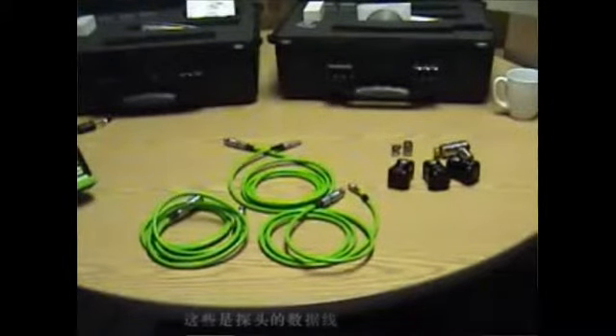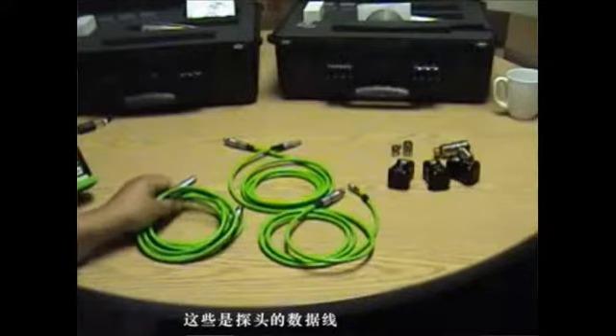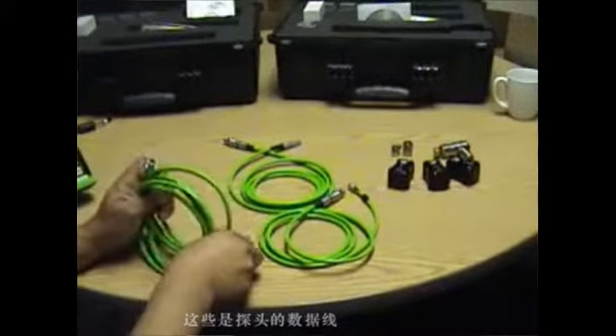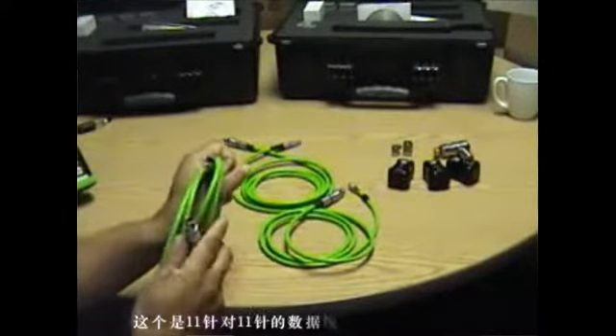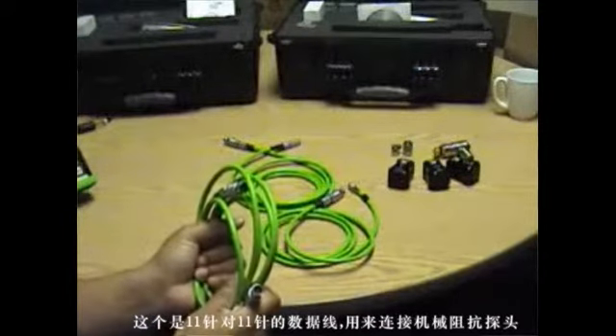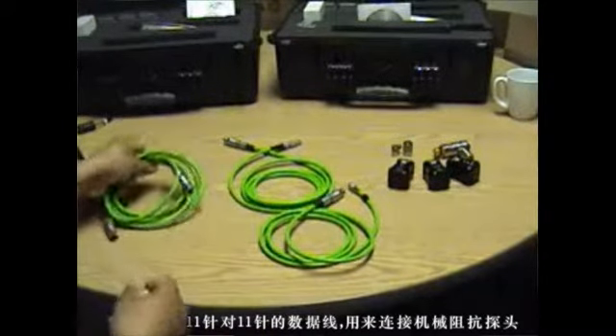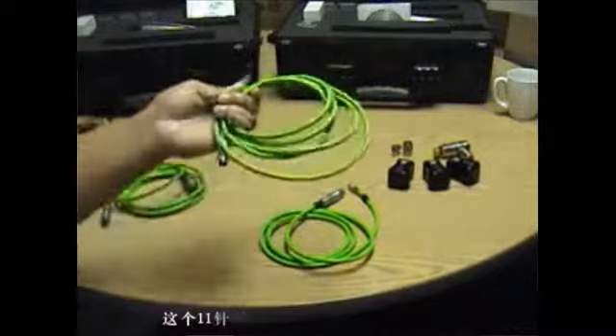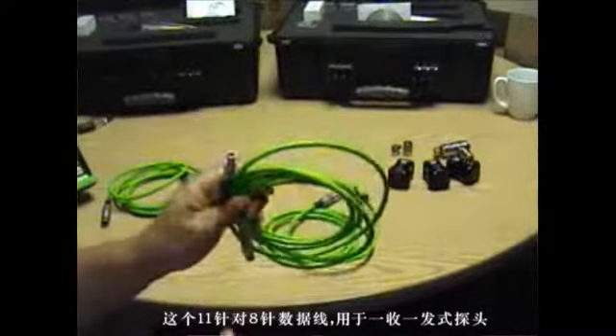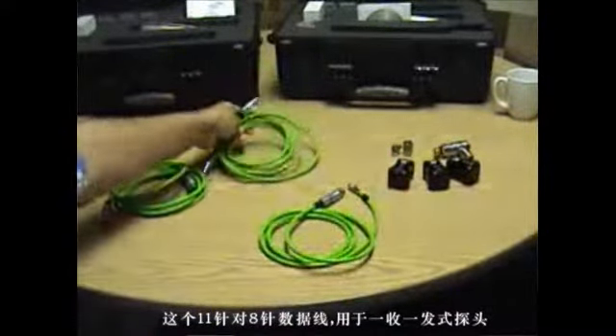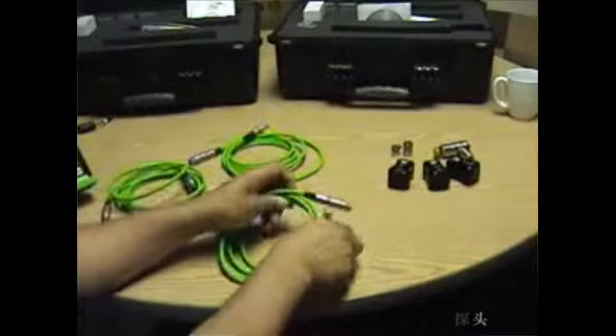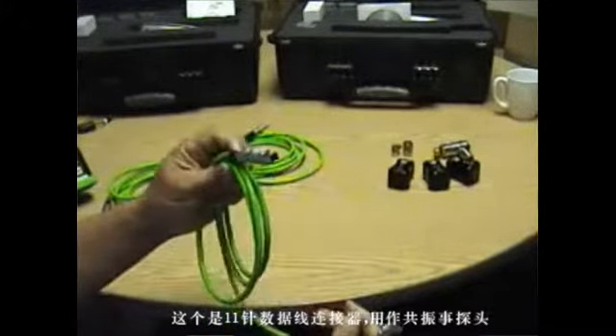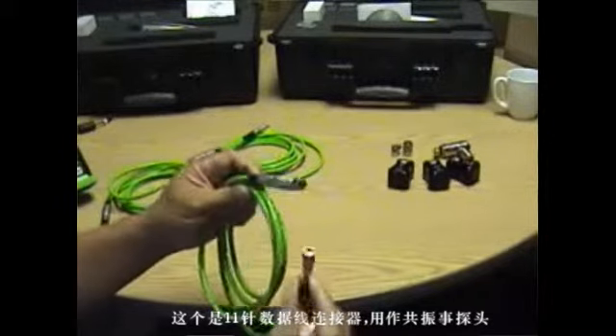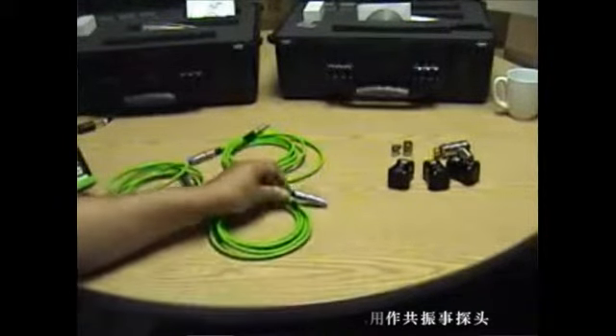These are the probe cables. This is the 11 pin to 11 pin that will be used with the mechanical impedance probe. This is the 11 pin to 8 pin probe that will be used with the pitch catch probes. And this is the 11 pin connector that will be used with the resonance probes.